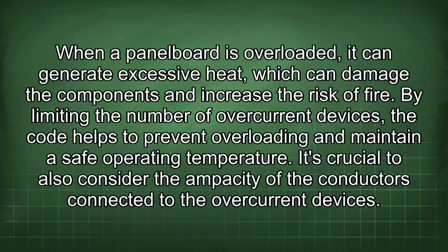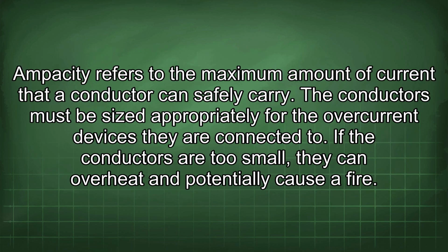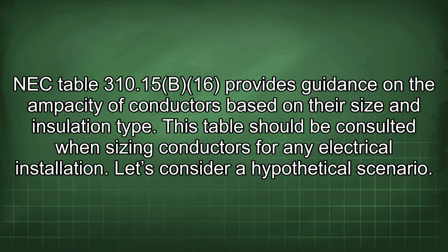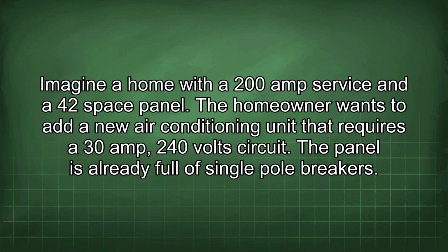It's crucial to also consider the ampacity of the conductors connected to the overcurrent devices. Ampacity refers to the maximum amount of current that a conductor can safely carry. The conductors must be sized appropriately for the overcurrent devices they are connected to. If the conductors are too small, they can overheat and potentially cause a fire. NEC Table 310.15(B)(16) provides guidance on the ampacity of conductors based on their size and insulation type. This table should be consulted when sizing conductors for any electrical installation. Let's consider a hypothetical scenario. Imagine a home with a 200 amp service and a 42 space panel.